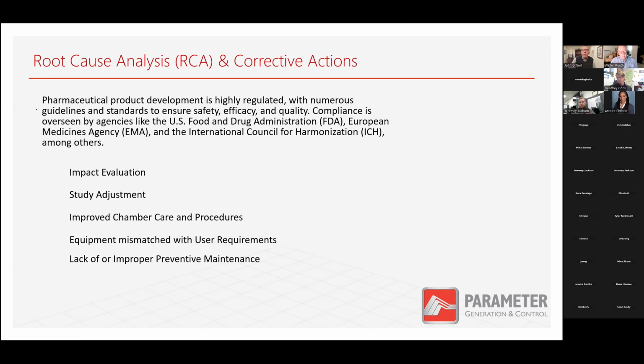We do have a chat question that asks, in this example, was there a temperature alarm prior to the discovered flood? The answer to that in the article, yes, there was. It says that there was a response by a metrology associate. He urgently attended it, and he found that the heating system had failed and temperature had decreased, and more seriously, the chamber was flooded. So apparently, in this scenario, it happened quite quickly, but yes, there was an alarm.